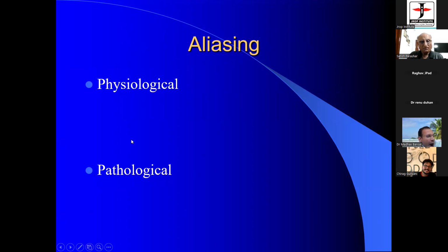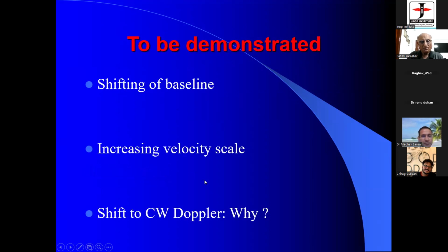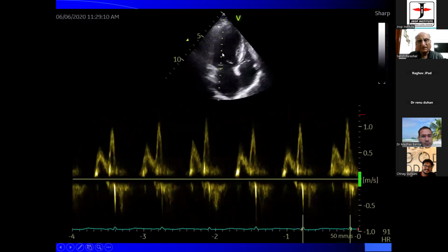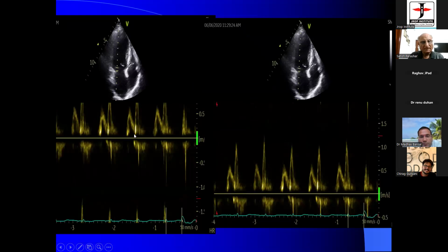Again, for the time, shifting of the baseline, and when to do a CW Doppler is written there. Just to give you an example: this is the mitral valve. This is above the baseline, and this is below the baseline. The zero line shows 1 meter per second. If you put the baseline above, the velocity will increase down below because it is in the opposite direction. Now see, we have taken it above. The velocity here becomes 1.2, here becomes 0.5, and this opposite thing occurs.